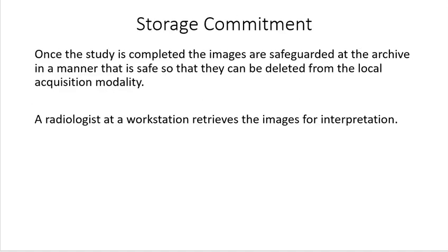Storage commitment. Once the study is completed, the images are safeguarded at the archive in a manner that is safe so that they can be deleted from the local acquisition modality. The radiologist at a workstation retrieves images for interpretation. Basically, PACS says, hey, I've got that CT you sent me, I'm now storing it. You don't need to hold it on the CT scanner anymore, and you can delete it from the acquisition modality.